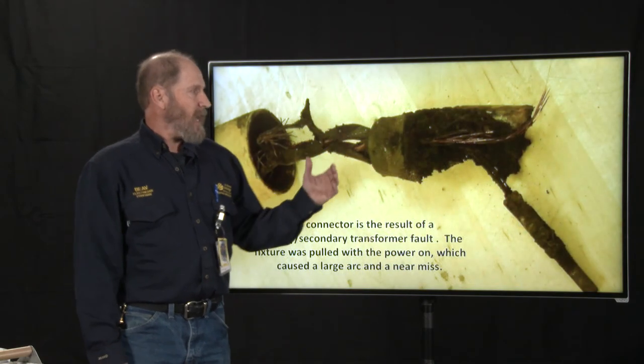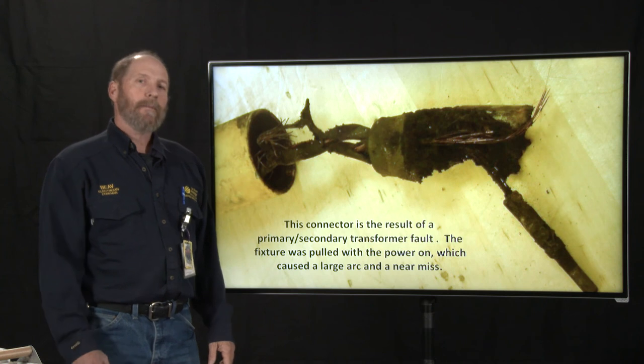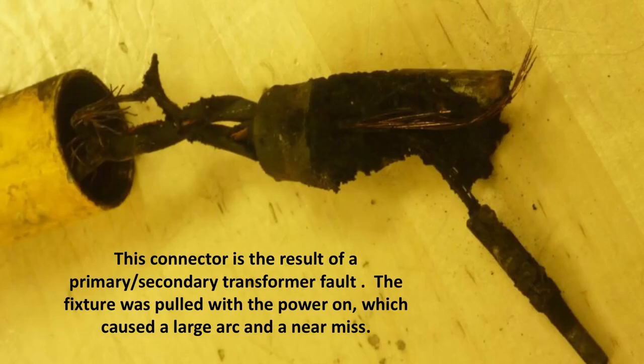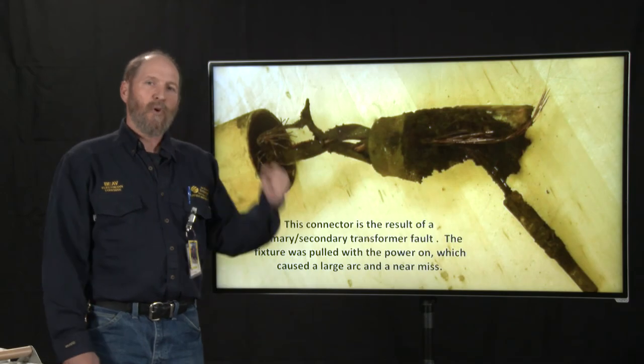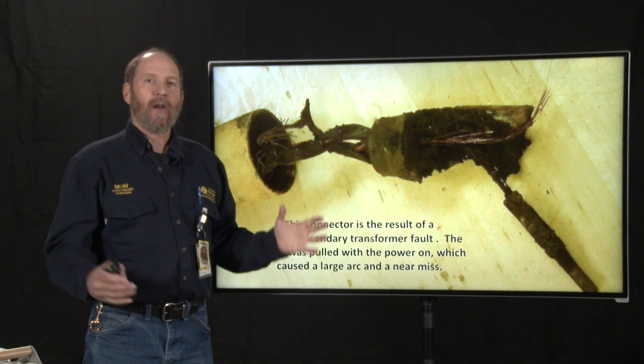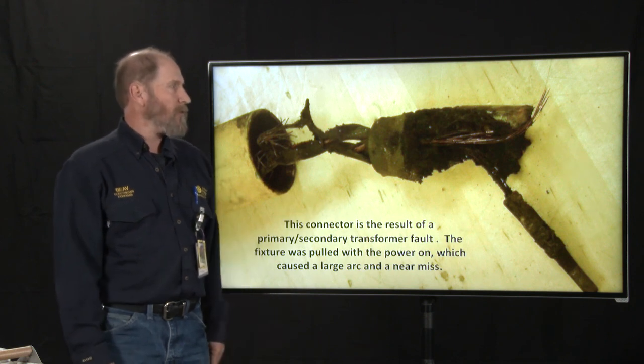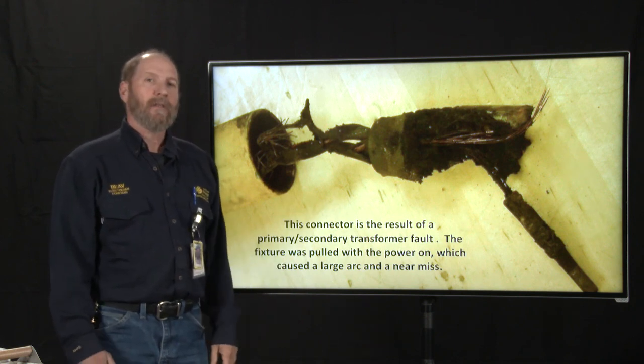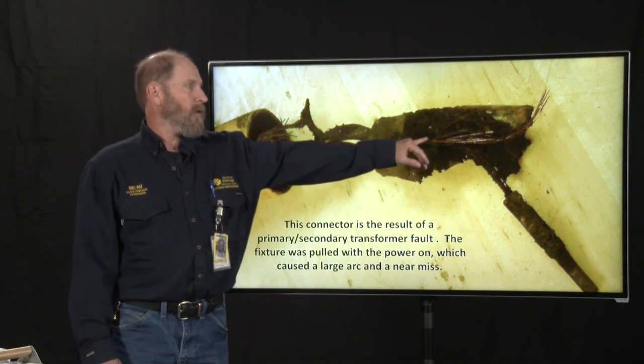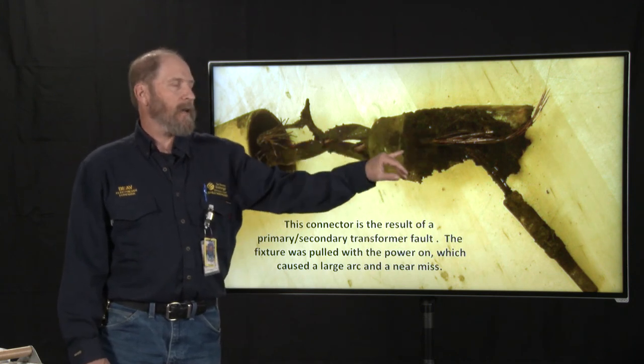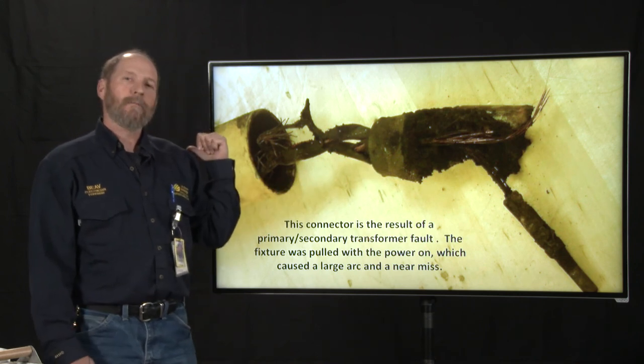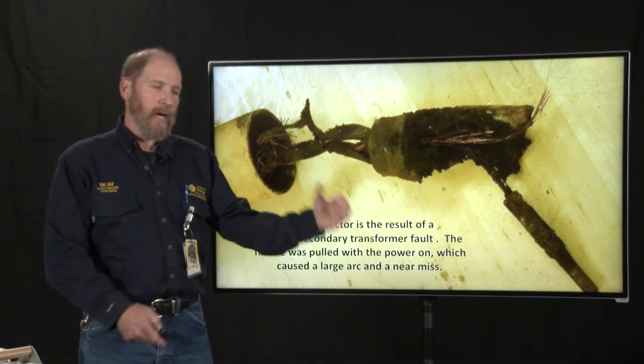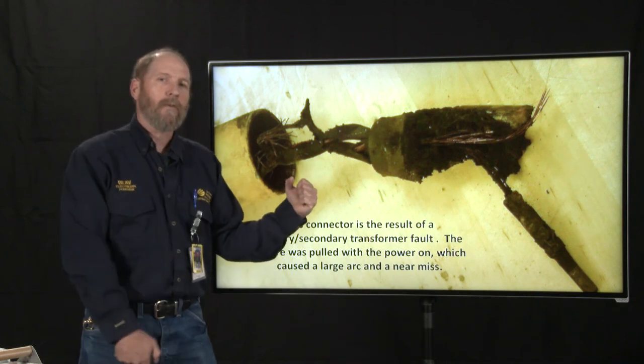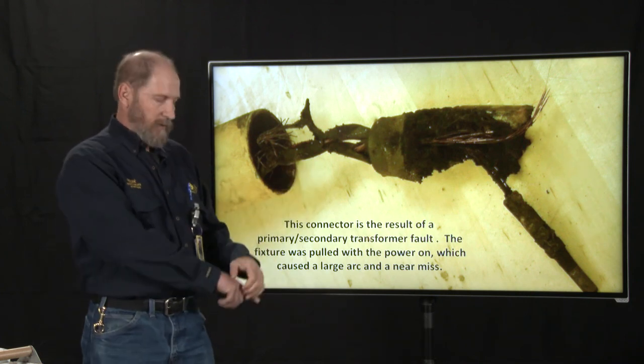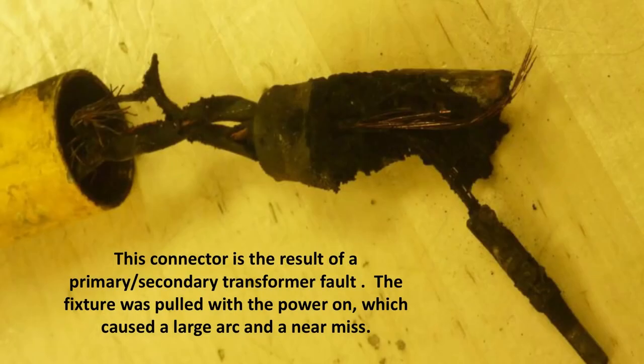This is a connector for a taxiway edge light from Anchorage International Airport. One of our electricians saw this light was out, replaced the bulb, it didn't work, so he just pulled it out of the ground. A big fireball came out at his feet. This was a very close call. It had a primary secondary fault in the transformer, but luckily it was blowing out to ground right at the connector and not at the top of the light fixture. Had it been higher in the light fixture and he had been pulling it out, it would have gone through him to get back to ground. As it was, it just blew across in the ground. So it was a close call.